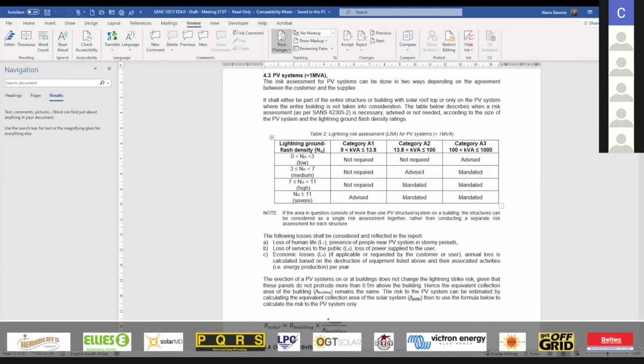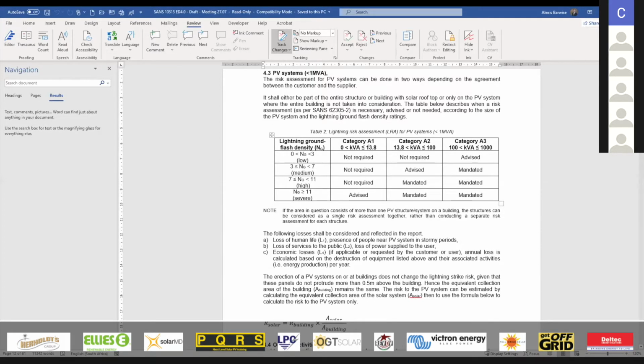So what we've done is look at multiple risk assessments, run hundreds of models, and come up with a matrix to give guidance on when a risk assessment is even needed. We've followed your categories of part 1 and part 2: category A1, A2, and A3, along with low, medium, high, and severe lightning ground flash density values, which can be obtained from the Weather Service and also from both these standards, published in the annexure sections.